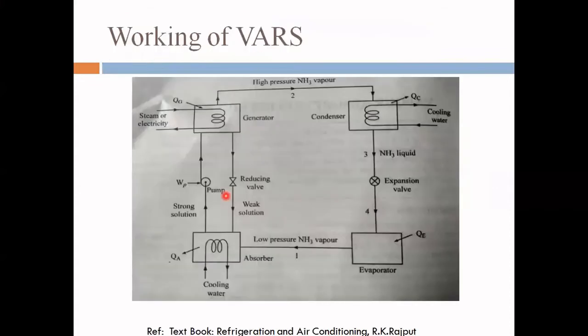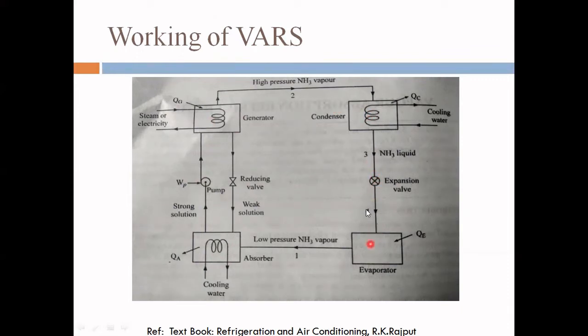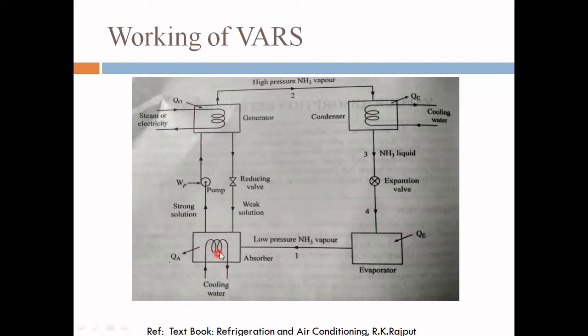Now for the working of the VARS: the parts are the absorber, generator, pump, and pressure reducing valve, followed by the condenser, expansion valve, and evaporator. The three components — condenser, expansion valve, and evaporator — are the same as in the vapor compression system. The four new components are the absorber, pump, generator, and pressure reducing valve. In the generator, steam or electricity is used to supply heat. In the absorber, cooling water is supplied to absorb the ammonia vapor.